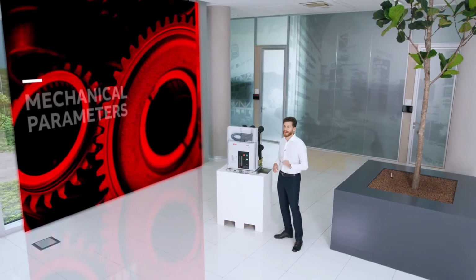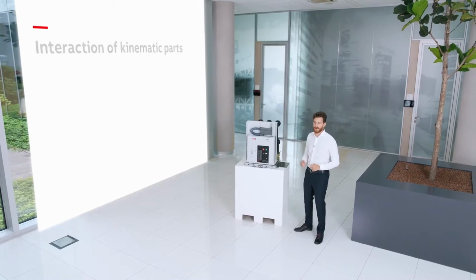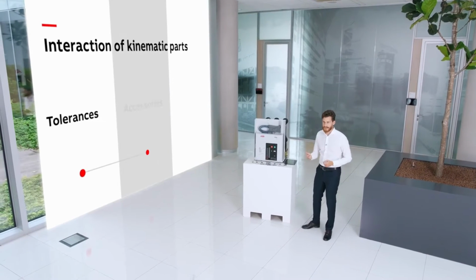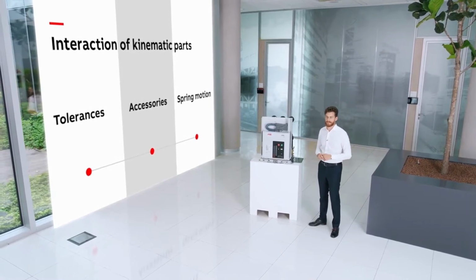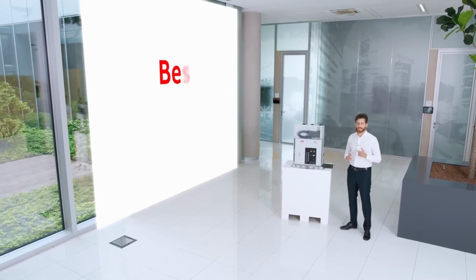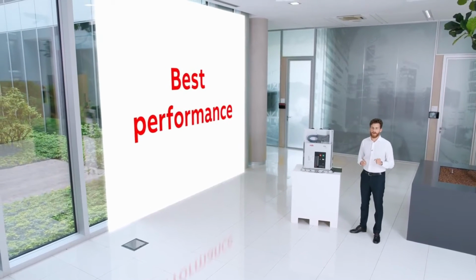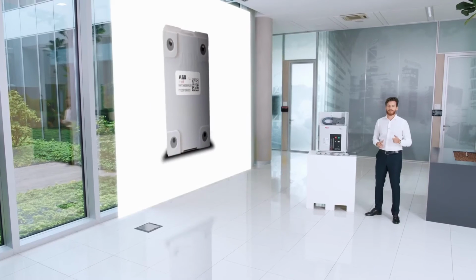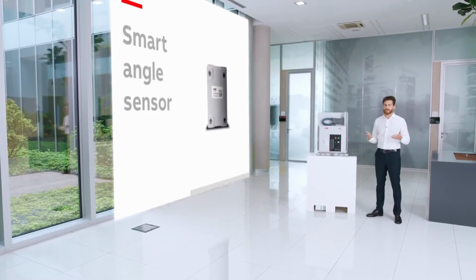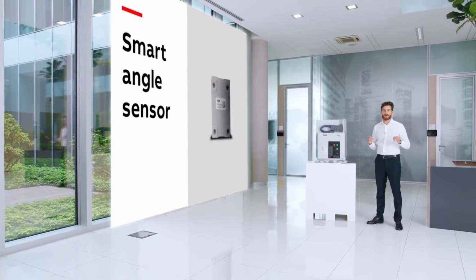Third, we have mechanical parameters. The circuit breaker trigger operation is the result of a complex interaction of kinematic parts, tolerances, accessories, and spring motion, pretty much like a clock. The whole kinematic chain needs to operate within design prescriptions to guarantee the best performance and long expected lifetime. We therefore positioned a precise angular sensor in its core that's able to detect the entire motion without interfering with performance in any way.